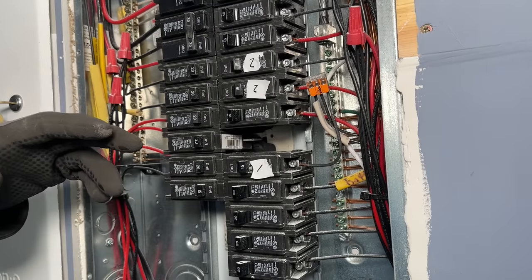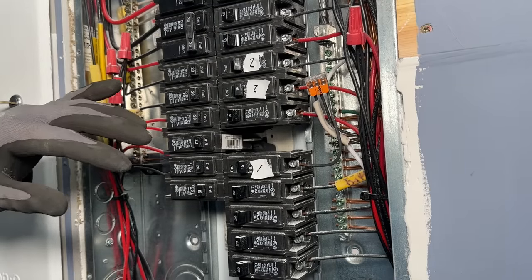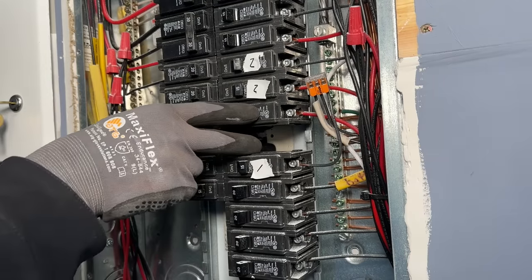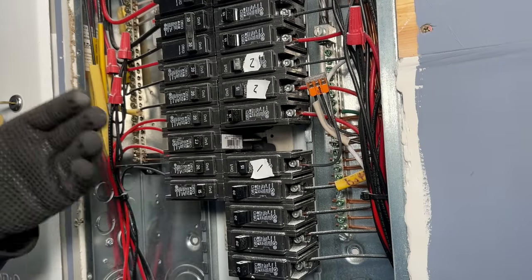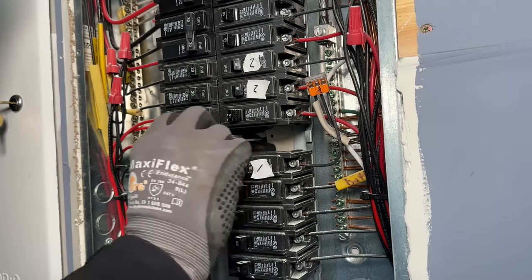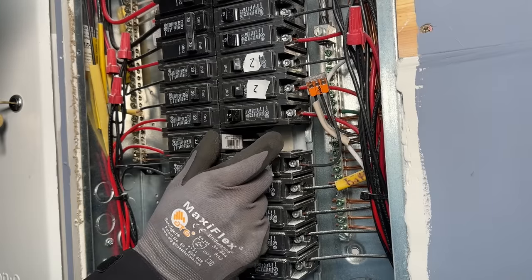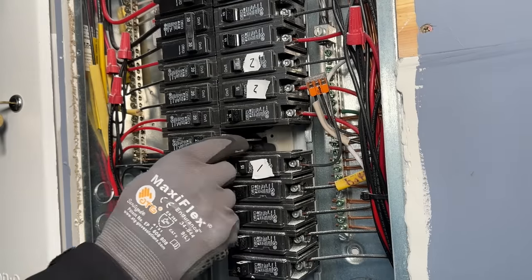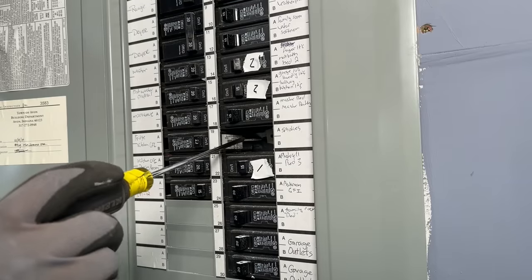If you're adding a 240-volt double-pole breaker, you might need to reshuffle the deck once your circuit combinations are complete to get two spaces side by side. Make sure you update your panel labels to maintain currency. If you're keeping the space open for future use, install a panel knockout cover to protect against accidental contact with live parts.